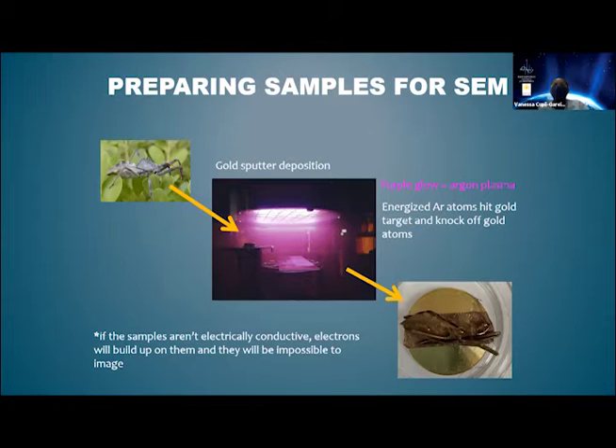And because electron microscopes require electrons, the material that's analyzed or looked at must be conductive. So to make our samples conductive, we coat them in gold using a sputter. A sputter is this instrument shown here in the middle. It has this mesh at the top made out of gold. And here, we coated this insect in gold. And how we do this is by pushing gas, in this case, argon gas, into the chamber. So you can think of the gas as a bag of popcorn, and the chamber as a microwave. When you put popcorn in a microwave, it heats up and the kernels move everywhere as they are turned into your fluffy popcorn.